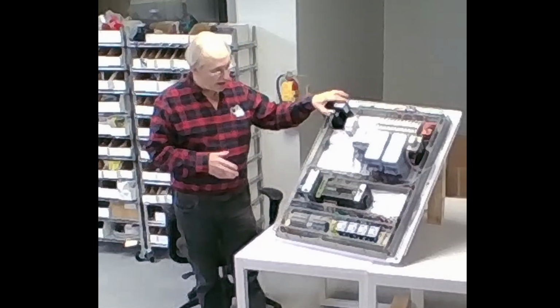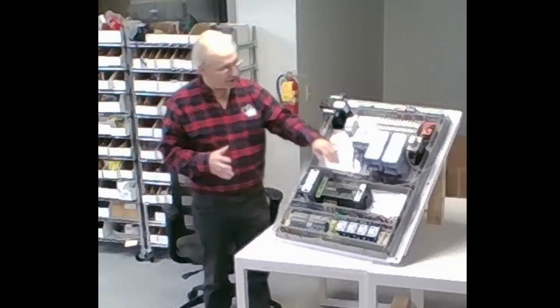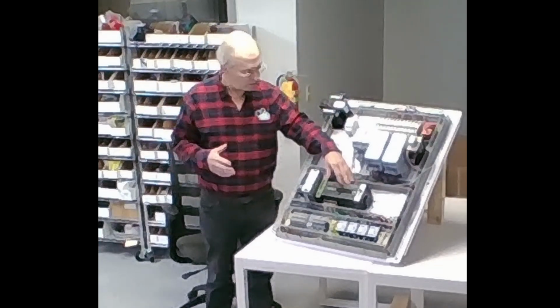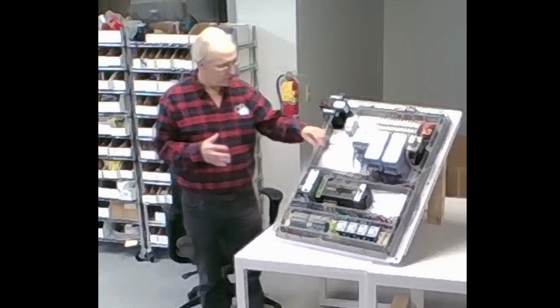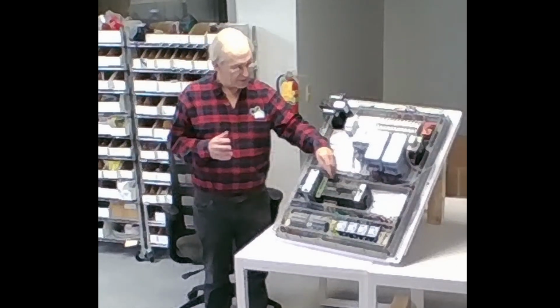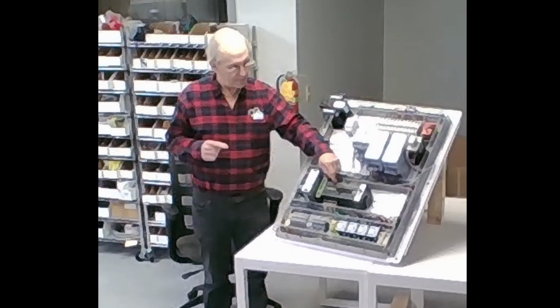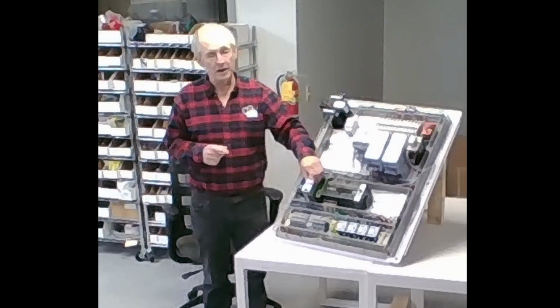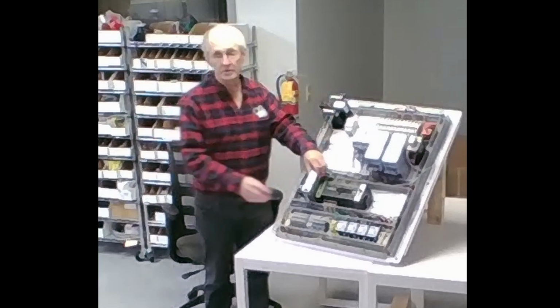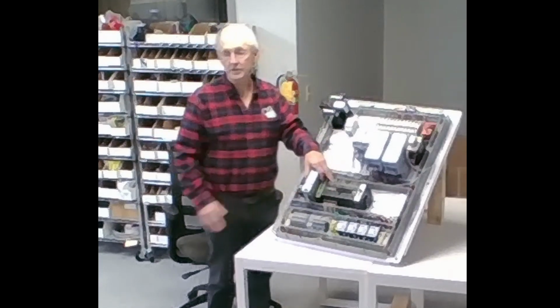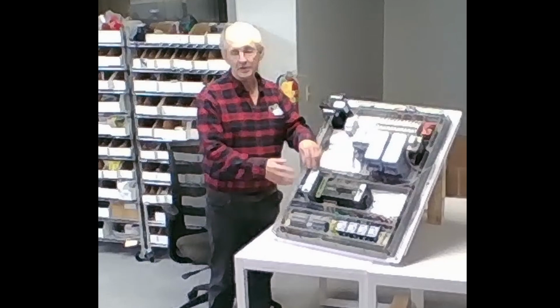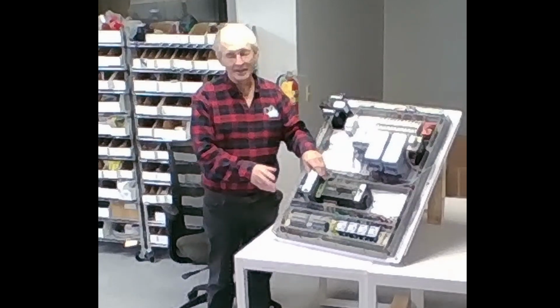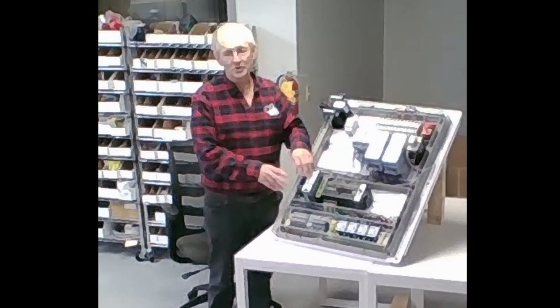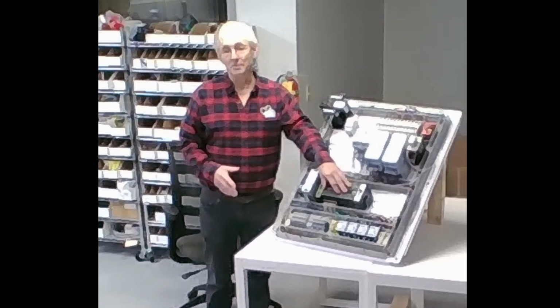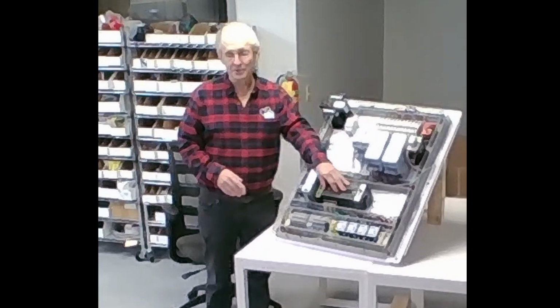And then I don't use PLCs with 120 volt input power. And the reason I don't is because I can hide the PLC behind another power supply that changes the AC to 24 volt DC and then run the PLC off of that. And that's just an added level of protection. If I get struck by lightning, I want as many things to get cooked before they get to the PLC, which is the brain of the whole thing. So that's the reason for splitting things up this way.